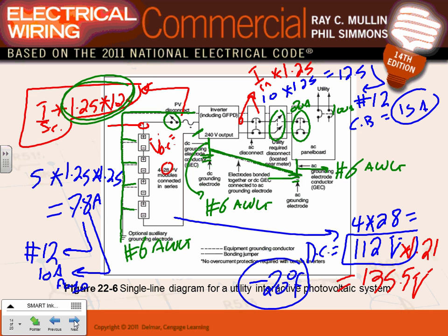What happens if you put a load? The voltage dips slightly. So you use the voltage open circuit, Jeff. And the current that we use when we size on the DC side is I short circuit. Meaning, here's a positive and a negative of one panel, and you tie the positive to the negative. The panel must be able to handle this short circuit current so the conductors cannot melt.